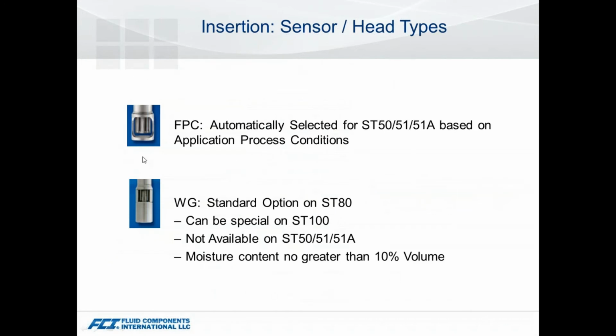So with that, there are some limitations. For a lot of our models, the higher end models, the ST80 to 100, you can select which type of head you want based on the application. But for the lower end models, the 50s, the 51s, based on your process conditions, you're going to either get that FP head or the FPC head. When you go above 50 pounds or so, we're going to automatically give you that FPC head.